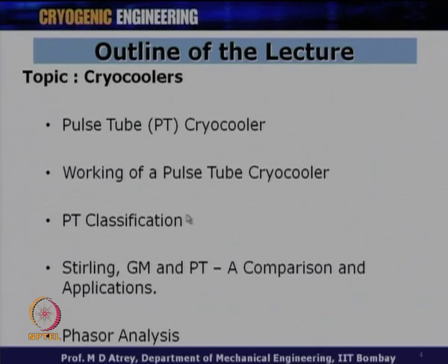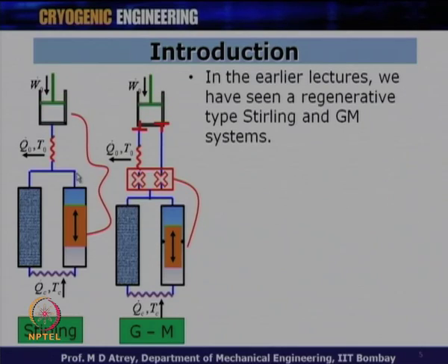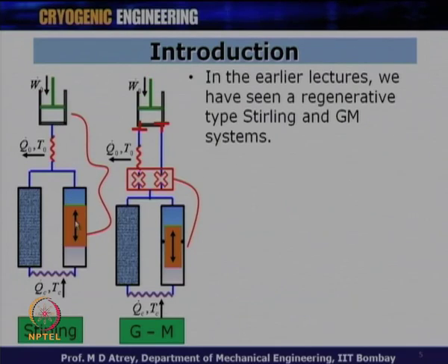The next lecture will also be dedicated to the pulse tube cryocooler, where we can see more hardware generated in our laboratory. To recap, we have seen regenerative cryocoolers of different types — Stirling type and GM type. In a Stirling cryocooler, there is no valve between the compressor and expander, so the displacer moves at the same frequency as the compressor piston with a fixed phase difference. In a GM cryocooler, there is a valve mechanism between the compressor and expander.